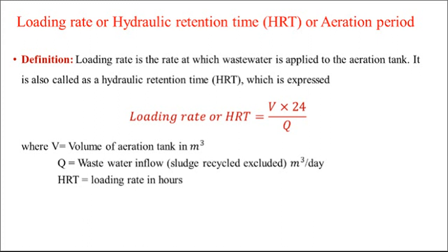It is also called hydraulic retention time, that is HRT, and is expressed as: loading rate or HRT is equal to the volume of the aeration tank divided by the discharge rate to the aeration tank, into 24 hours, where V is the volume in cubic meter, Q is the wastewater inflow to the aeration tank, and HRT is the loading rate in hours.